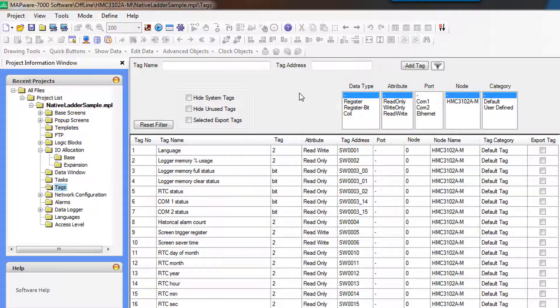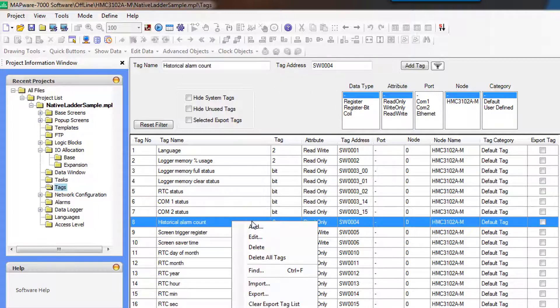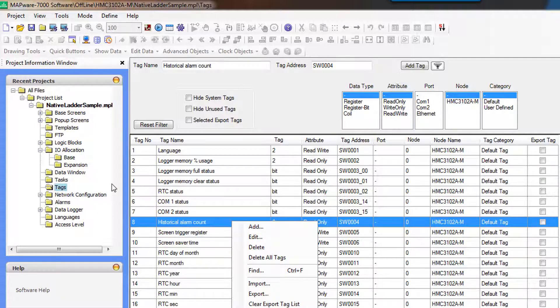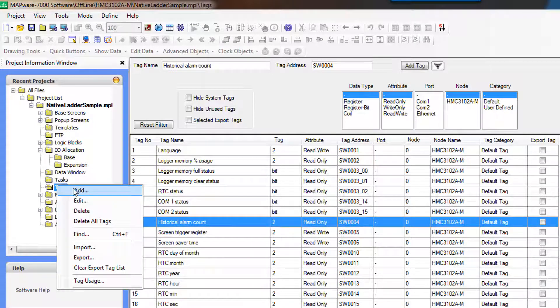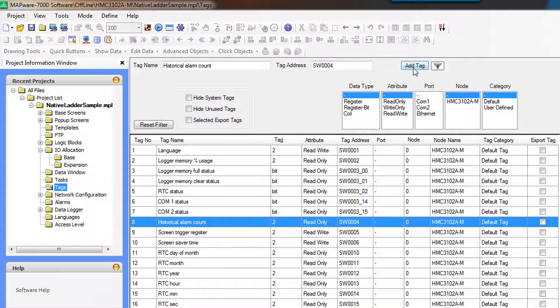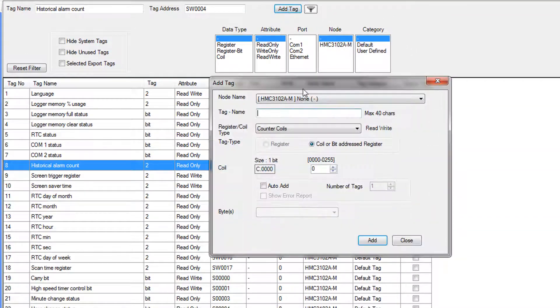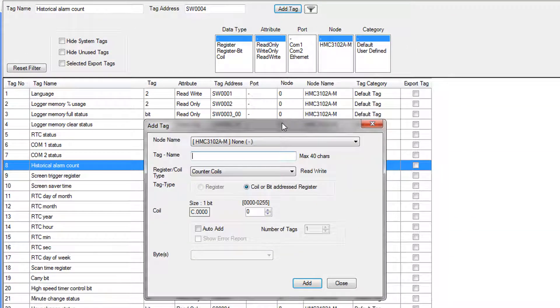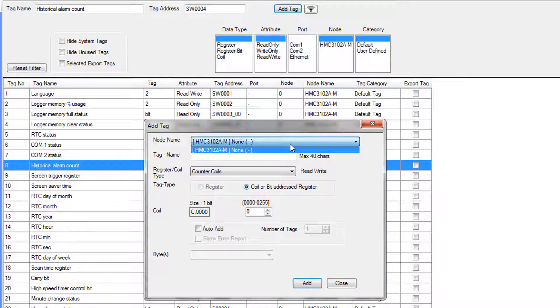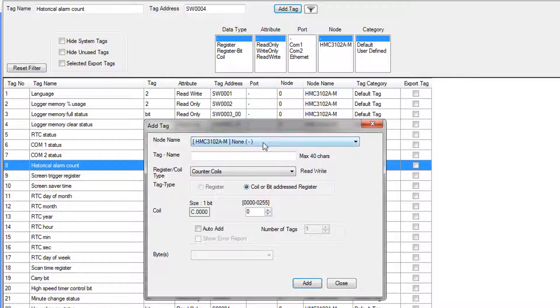We need to add some tags to our project. You can do this by right-clicking and going Add from this menu, from over here, or by clicking this button up here. This brings up the Add Tag window. So the fields in this Add Tag window, this is the node name. Again, if you had an external PLC that you were communicating with, it would show up in this drop-down.